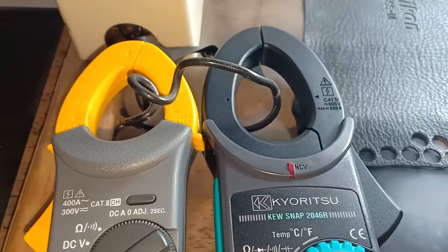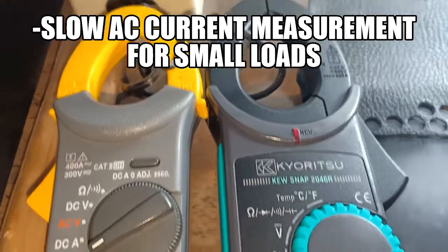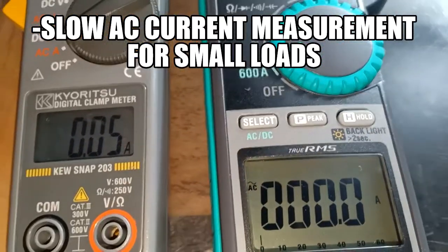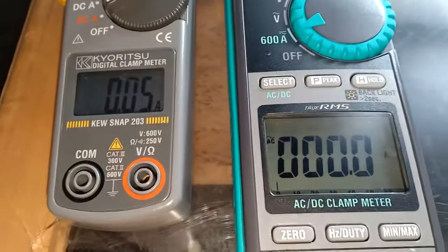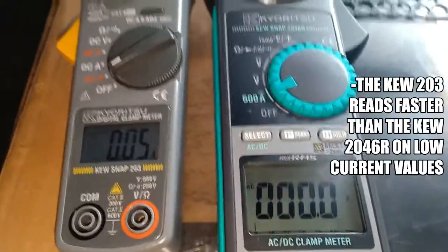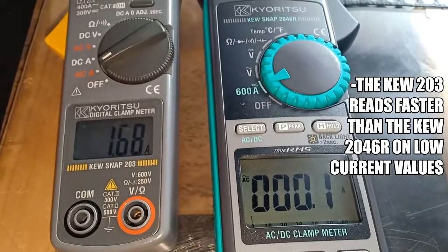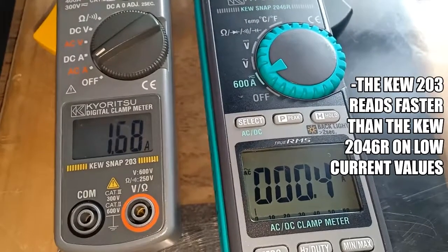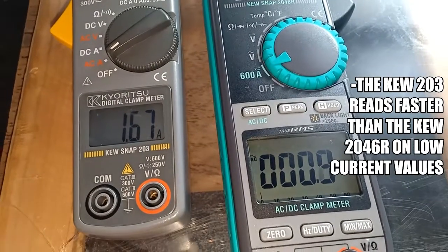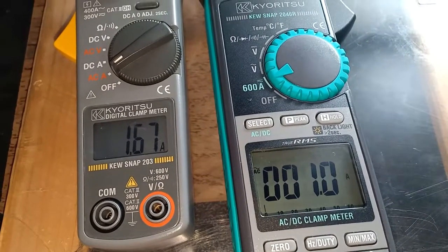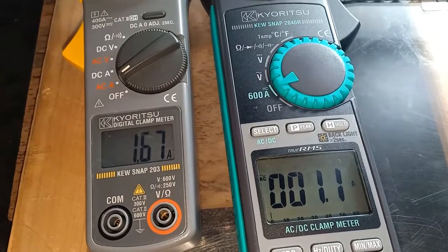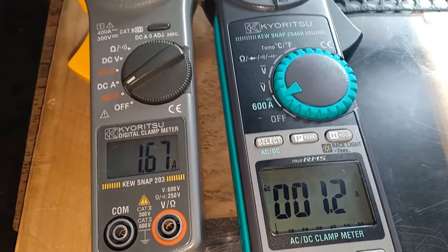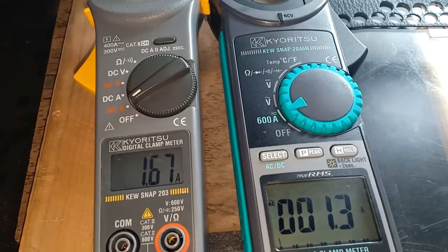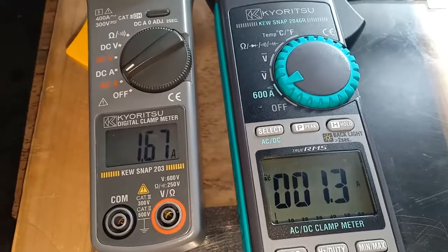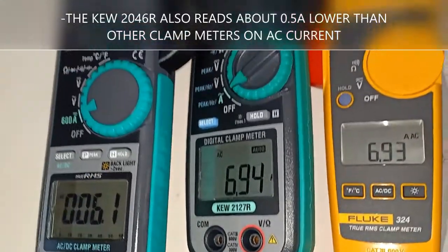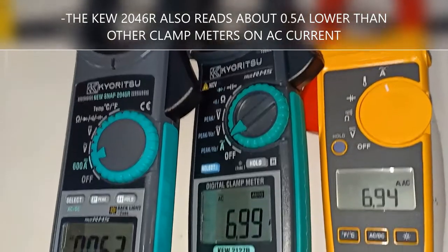Here are some of the things that I wasn't too excited about. I observed that AC current measurement of low values was rather slow. I noticed this when I compared its readings with the readings of my other clamp meters when testing AC current in the range of about 3 amperes AC to 6 amperes AC. It was also lower by about 0.5 amps, which should not be much of a concern if you're troubleshooting. But if you're trying to configure a small protective device based on high resolution accuracy, this can be an issue. Current above 6 amperes AC, however, were displayed with minimal delay. There are no problems there.